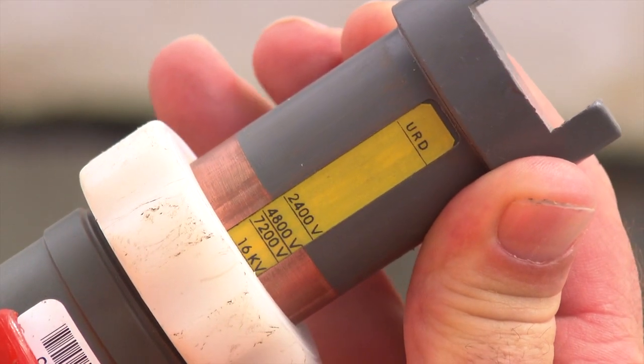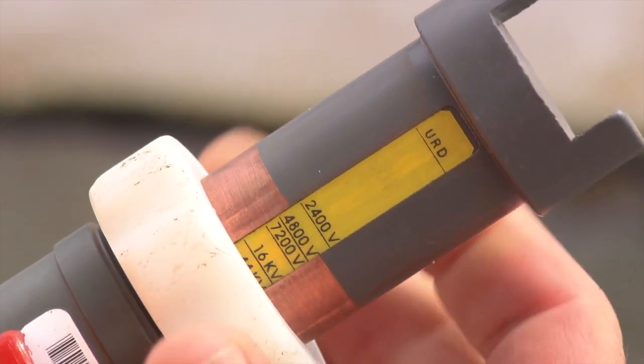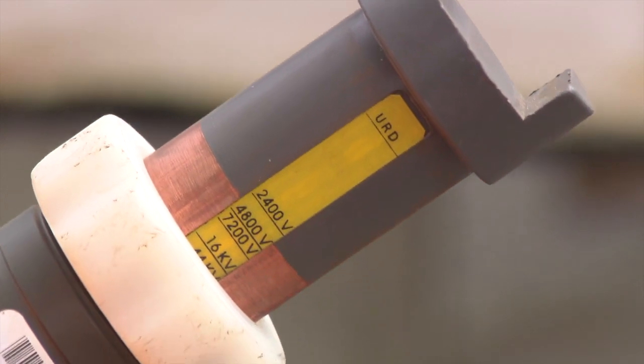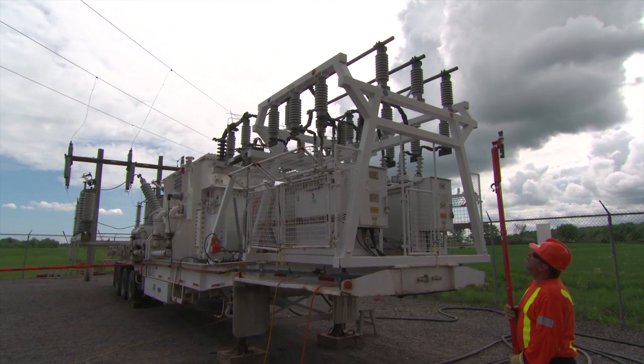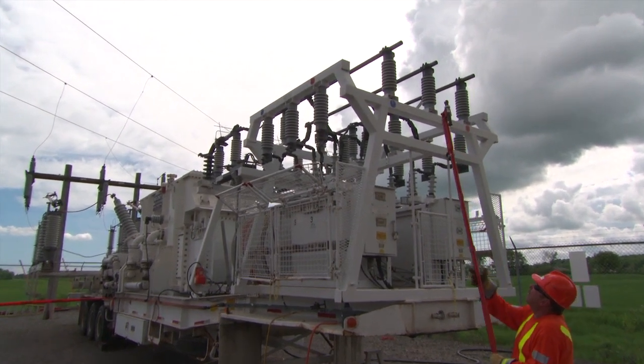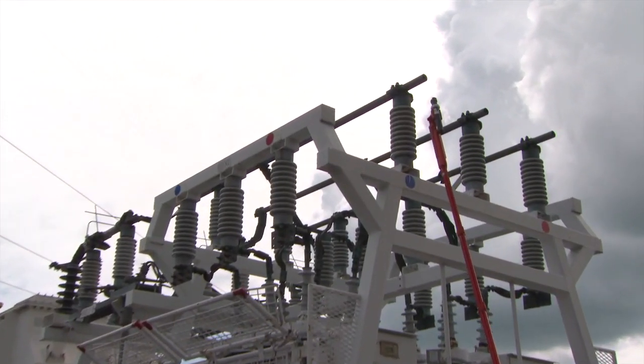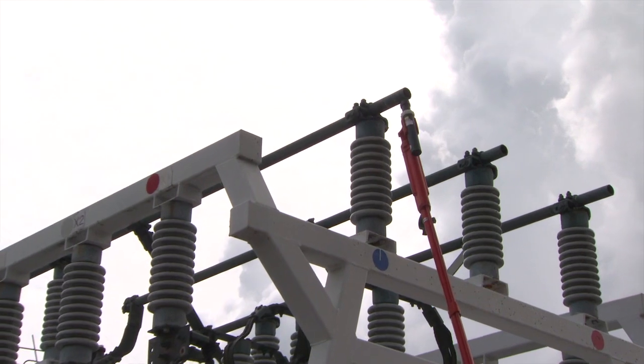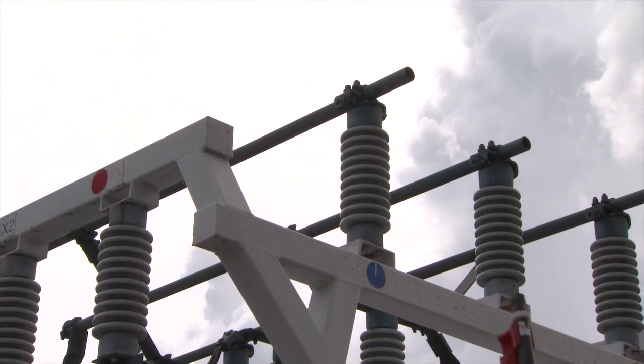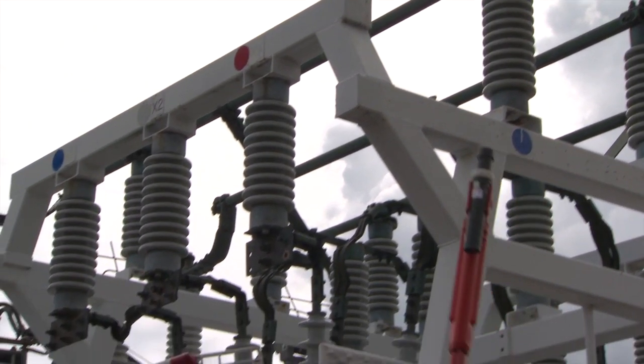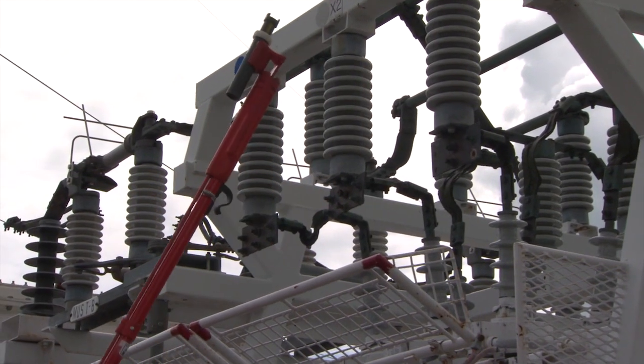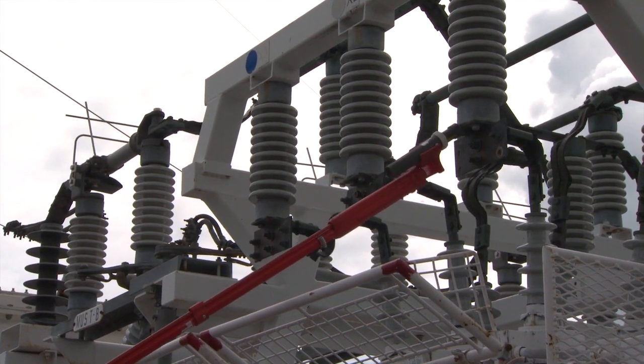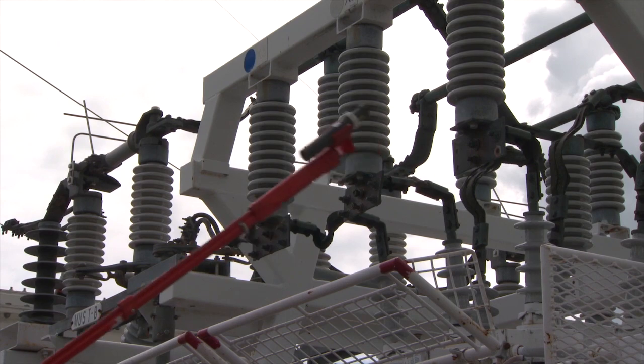Verify zero potential on the F1 load terminals with an approved LIV tester. Set the LIV to the correct operating voltage and test it on a live circuit first to ensure it functions correctly. Repeat the same close trip operation again on the F2 recloser to verify the recloser is open and the springs are discharged. Then check F2 for zero potential using an LIV.